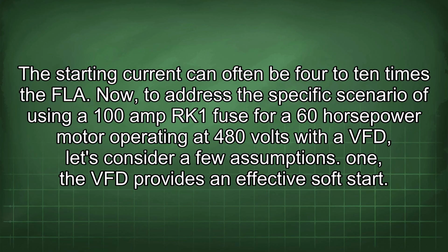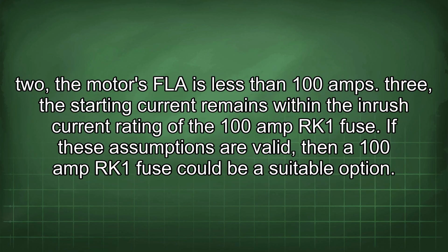Now, to address the specific scenario of using a 100 amp RK1 fuse for a 60 horsepower motor operating at 480 volts with a VFD, let's consider a few assumptions. 1. The VFD provides an effective soft start. 2. The motor's FLA is less than 100 amps. 3. The starting current remains within the inrush current rating of the 100 amp RK1 fuse. If these assumptions are valid, then a 100 amp RK1 fuse could be a suitable option.